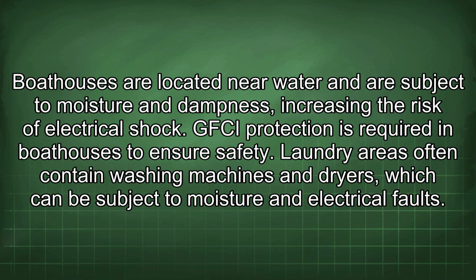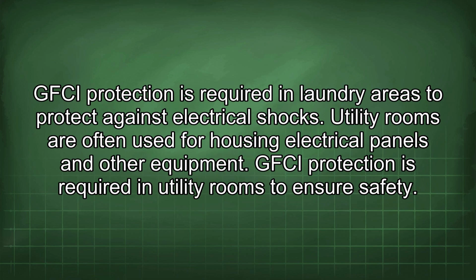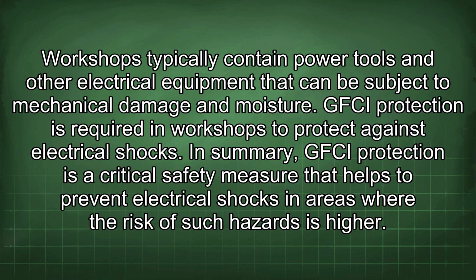Boathouses are located near water and are subject to moisture and dampness, increasing the risk of electrical shock. GFCI protection is required in boathouses to ensure safety. Laundry areas often contain washing machines and dryers, which can be subject to moisture and electrical faults. GFCI protection is required in laundry areas to protect against electrical shocks. Utility rooms are often used for housing electrical panels and other equipment. GFCI protection is required in utility rooms to ensure safety. Workshops typically contain power tools and other electrical equipment that can be subject to mechanical damage and moisture. GFCI protection is required in workshops to protect against electrical shocks.